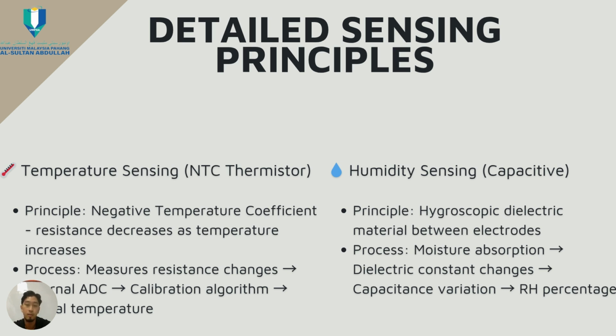Next is the humidity sensing principle. The humidity sensor uses a capacitive sensing element made of hygroscopic dielectric material placed between two electrodes. When humidity changes, the dielectric material absorbs or releases moisture, changing its dielectric constant. This changes the capacitance between the electrodes, which is measured and converted to a relative humidity percentage.